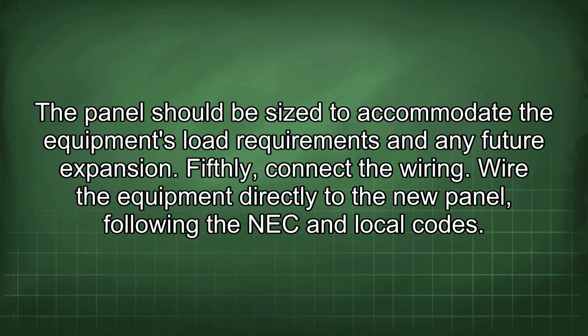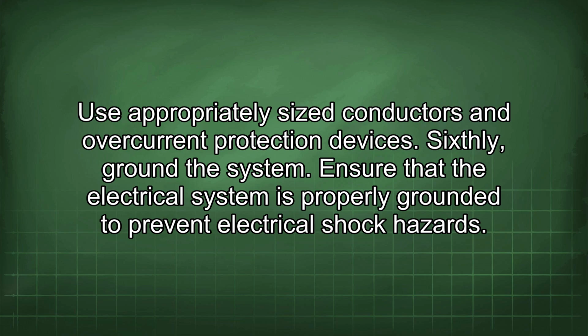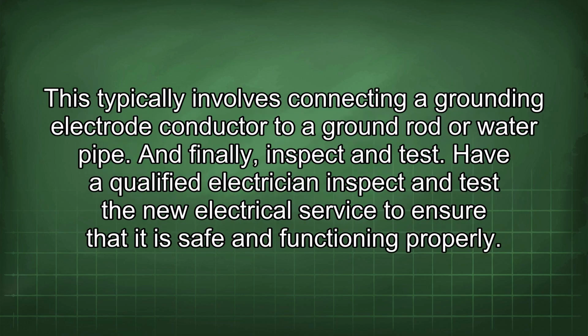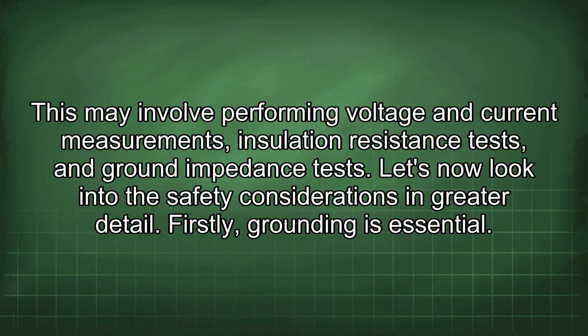Fifthly, connect the wiring. Wire the equipment directly to the new panel following the NEC and local codes. Use appropriately sized conductors and overcurrent protection devices. Sixthly, ground the system. Ensure that the electrical system is properly grounded to prevent electrical shock hazards. This typically involves connecting a grounding electrode conductor to a ground rod or water pipe. And finally, inspect and test. Have a qualified electrician inspect and test the new electrical service to ensure that it is safe and functioning properly. This may involve performing voltage and current measurements, insulation resistance tests, and ground impedance tests.